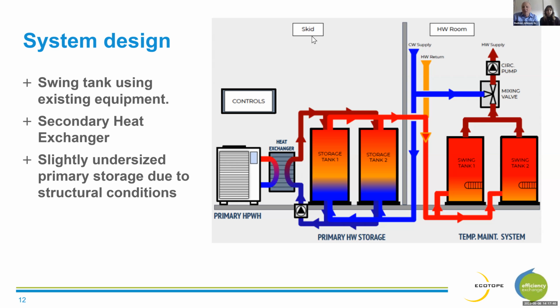And the control of that secondary heat exchanger is actually what's leading to our slightly under target performance, because the controls of that heat exchanger have to be just right to get as cold of water as possible going to the heat pump. And Madison will show some of the data that allowed us to figure that out and provide some feedback to Mitsubishi for product improvement.